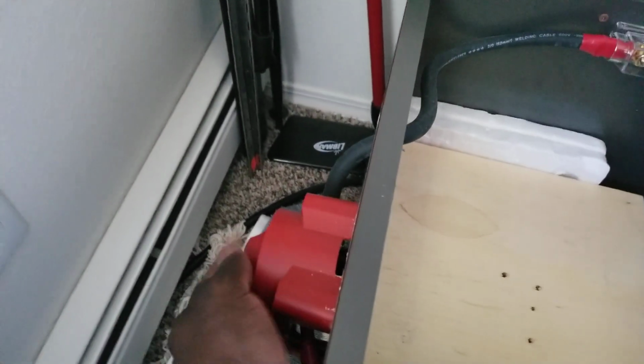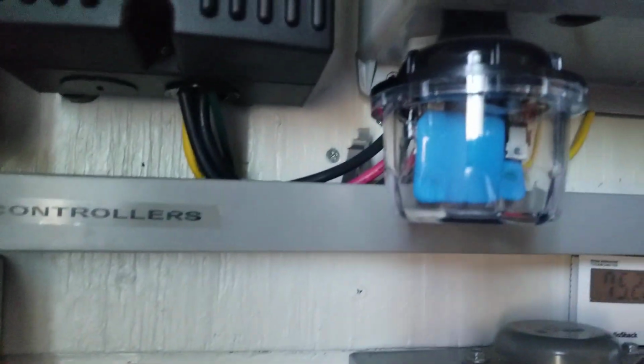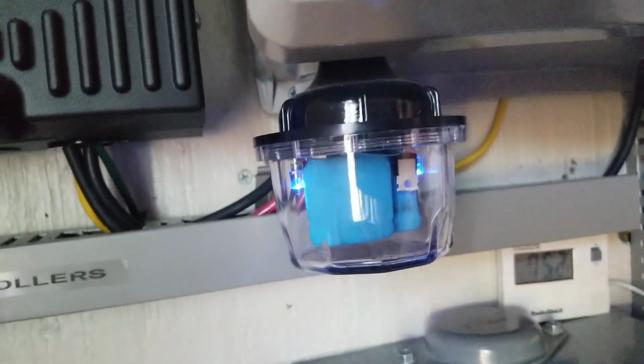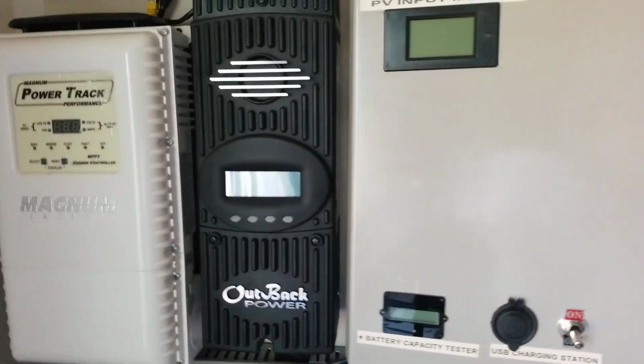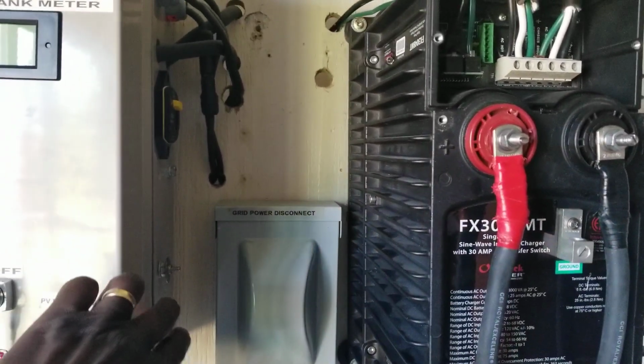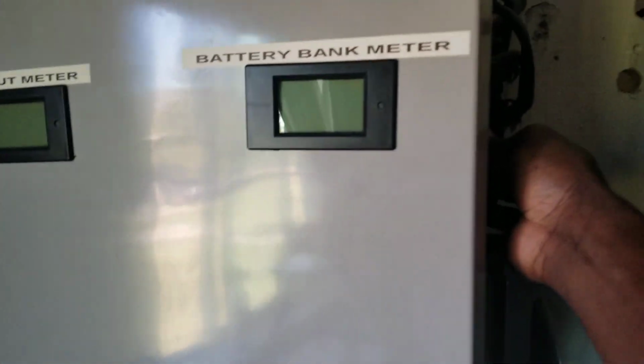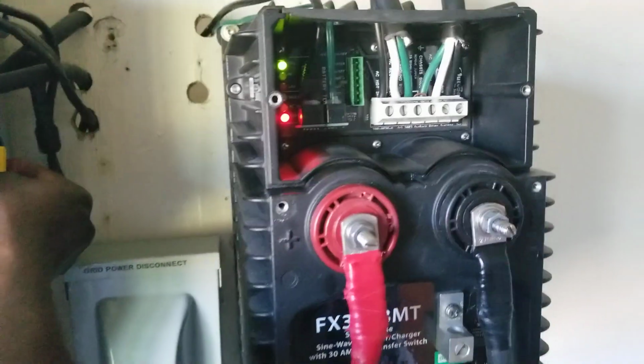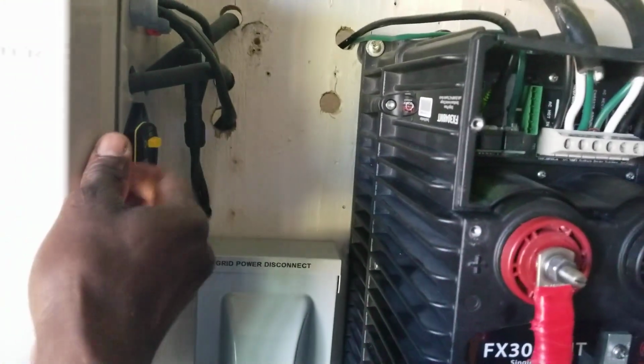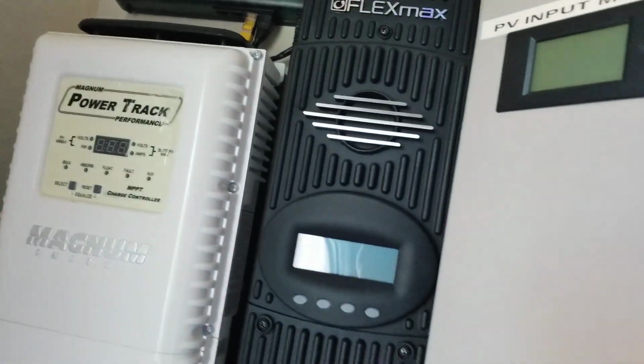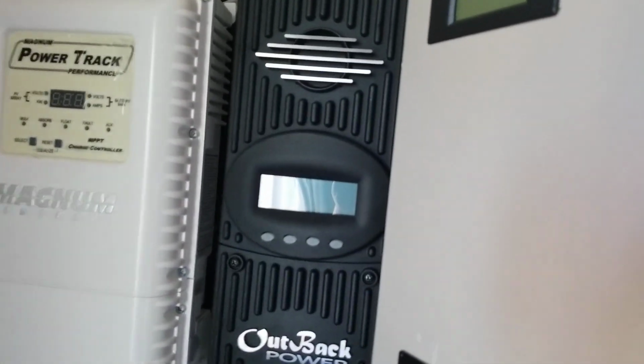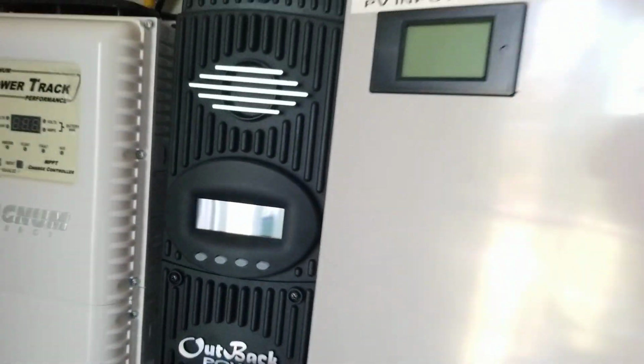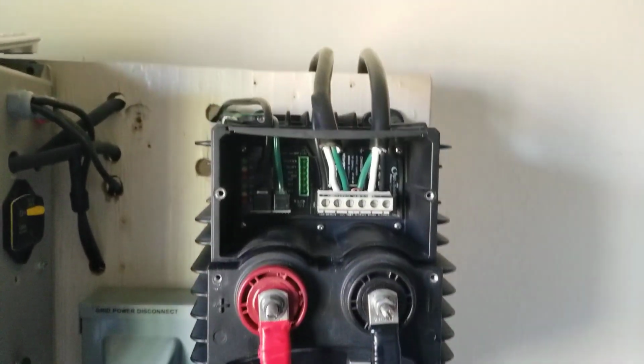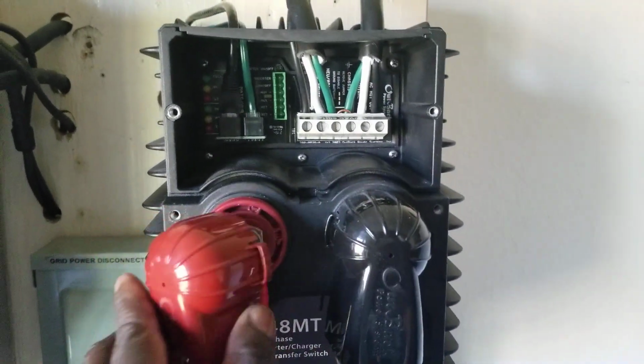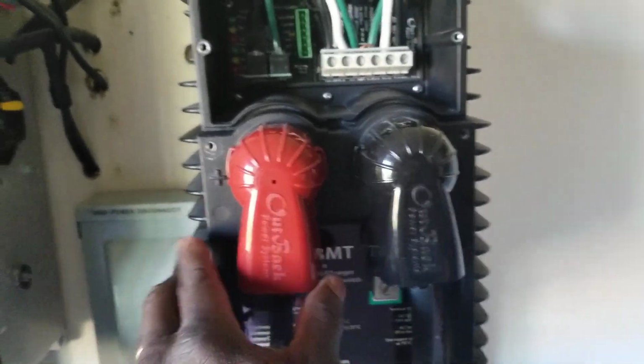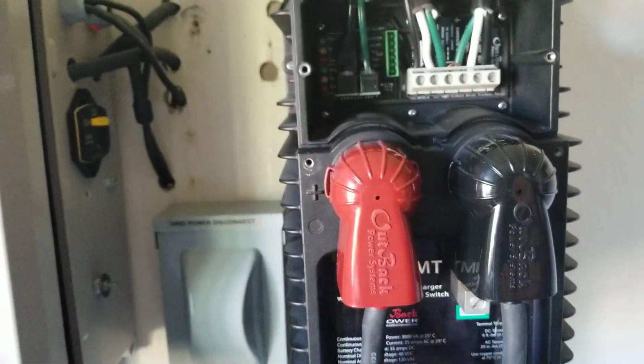We're back here, guys. This is the switch, the main switch, cutoff switch, and you can see if I turn it on, the lightning arrestor is on and the system is off. These guys are off, and if I turn the breaker for the inverter, it'll fire it up right away. Turn this one off. I still have to put the aux fan. I turn the breaker for the OutBack, it's on. Thank you. Let's go back and put the covers here, protect the terminals from touching the other cover that's gonna come here.